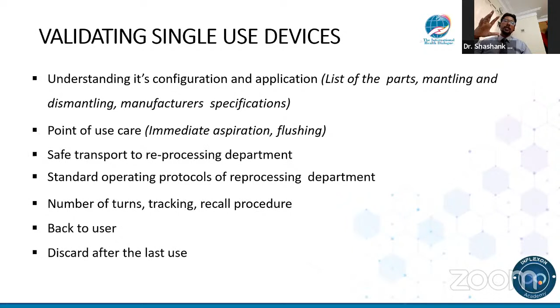Yeah, so as I said, at every stage of your process, you need to validate each step that is there. If you're looking at the responsibility of each of those departments, some of them may slightly vary, some of them may be a little different for each of your hospitals, but this is a general guideline: at every step of reusing a single-use device, validation and verification become very important, that you check what is happening. For example, if you want to check post cleaning, as madam said, you can use an ATP device, or after sterilization is over, you randomly pick certain devices, take a swab and check whether there is any growth. Can it be stored? How long can it be stored? Is the process being correct? All of that. And probably you may want to, at some point of time, look at some of the internal workings of some of these devices.